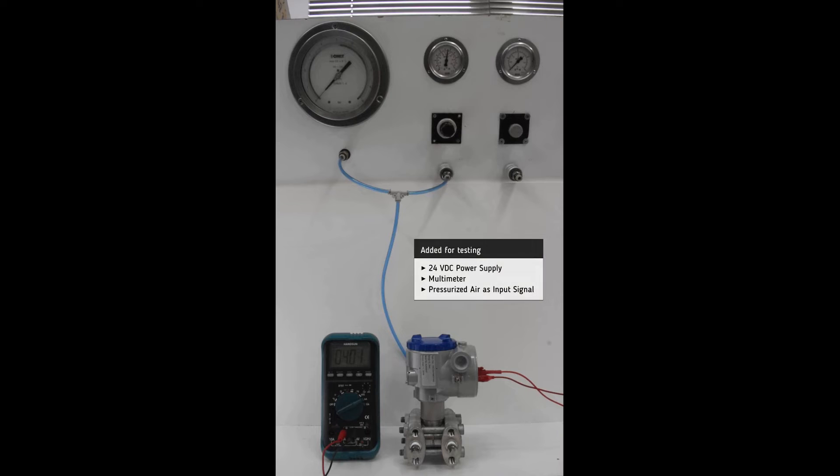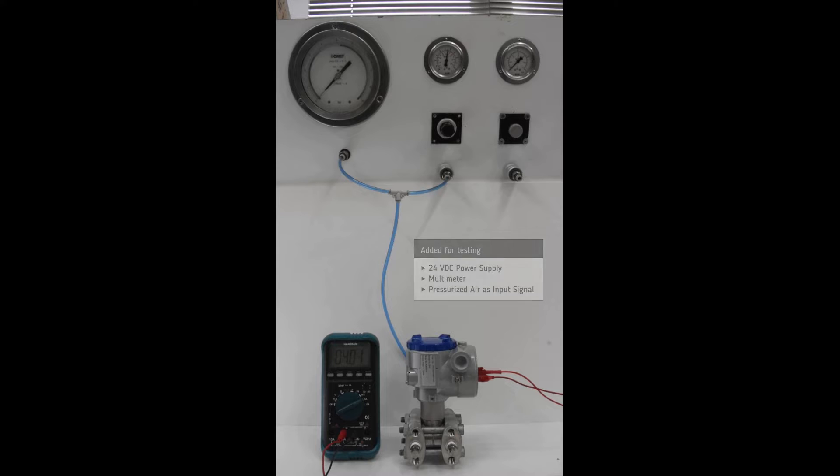For testing we add a 24 volt DC power supply, a multimeter in order to measure the milliamp output, and some pressurized air as input signal.